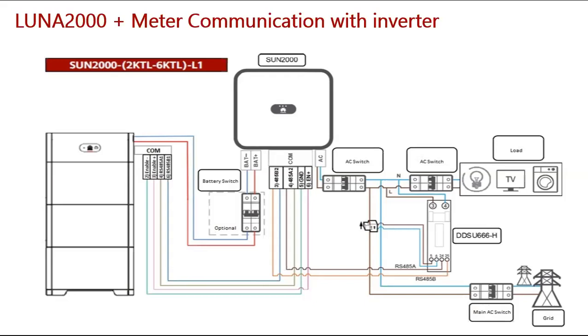As customers are installing the meter as well, the meter communication cable also goes into COM pins 3 and 4 of the inverter. So customers start getting confused about how they can connect two communication cables to one single pin. That's why we prepared this picture for you, to make it clear that you can connect the two communication cables, from the inverter and from the meter, and from the battery, to pin 3 and pin 4 of the inverter module.